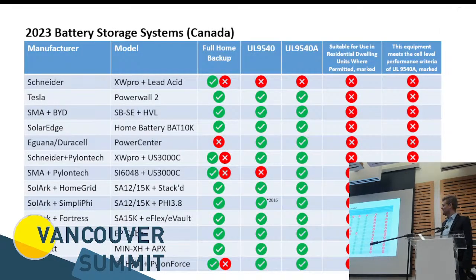The interesting part is what's available on the market, and the pretty bad thing here is that for use in residential dwellings or dwelling units to be permitted, you need to have it marked on the battery storage system that this equipment meets the cell level performance criteria of UL 9540A. None of the systems on the market right now have that labeling because they didn't pass. However, most of them at least pass UL 9540 and UL 9540A if you have a certain combination of inverter plus battery.